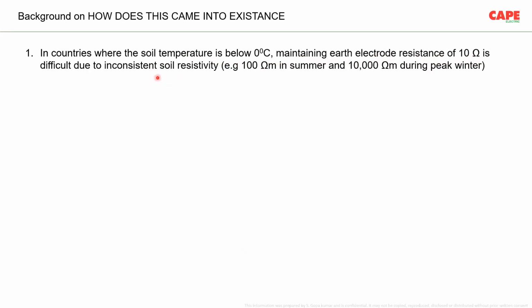What is this inconsistent soil resistivity? During summer, when there is rain and moisture in the soil, the resistivity is 100 ohm meter, whereas during peak winter the same soil can offer a resistivity of 10,000 ohm meter. So it is changing from 100 ohm meter to 10,000 ohm meter.